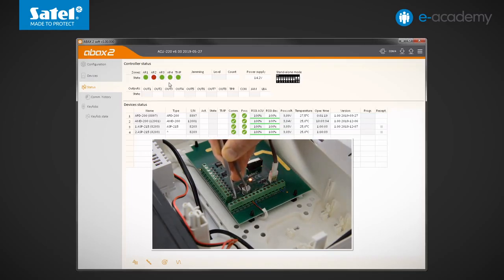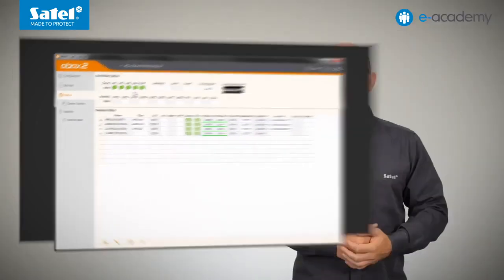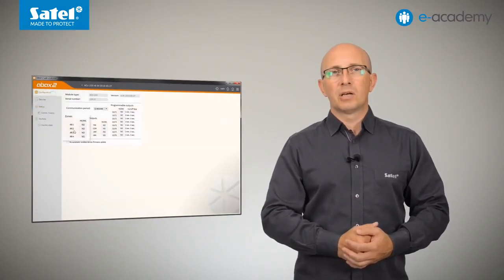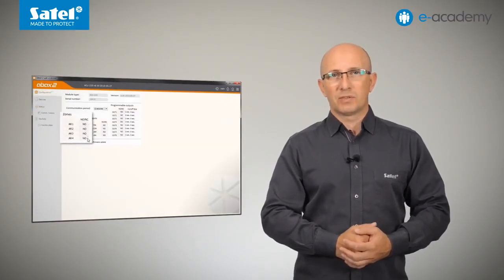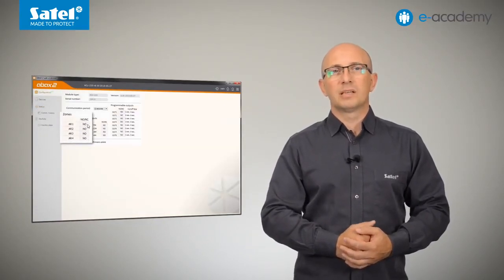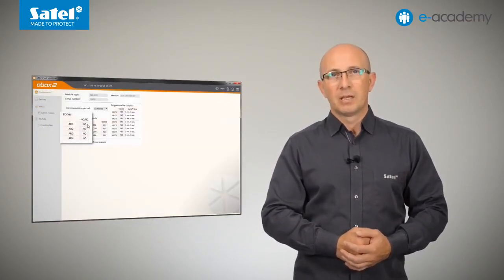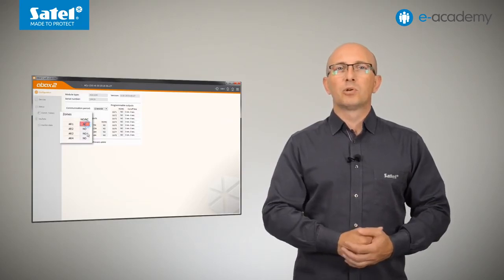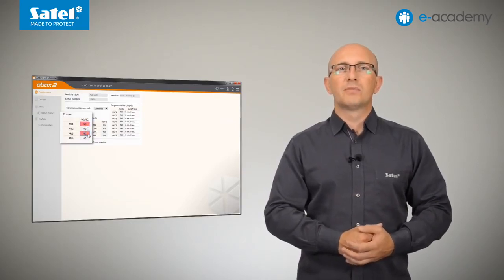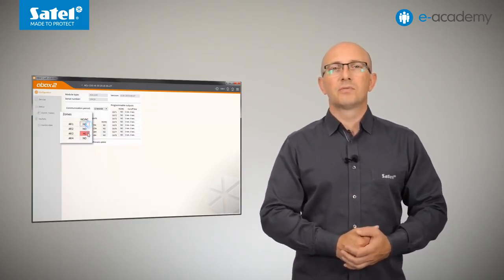It is worth remembering here that, as shown in the previous episode, individual zones and outputs of the ACU220 module can be programmed as NO, normally open, or NC, normally shortened to common ground or closed. To change their type, click twice on the selected field in the Configuration tab.